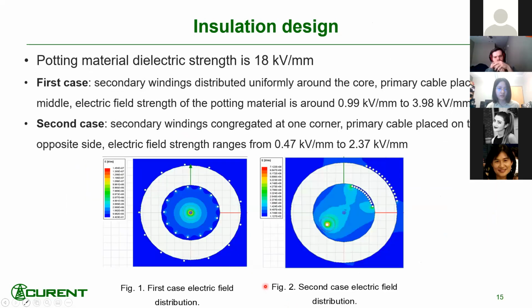And another part is to verify the insulation design. So I chose potting material that has an 18 kV per millimeter dielectric strength, and I simulate this cross-sectional view of the transformer, just to see the electric field distribution inside the cores and around the windings, to see if the field strength would exceed this limit.